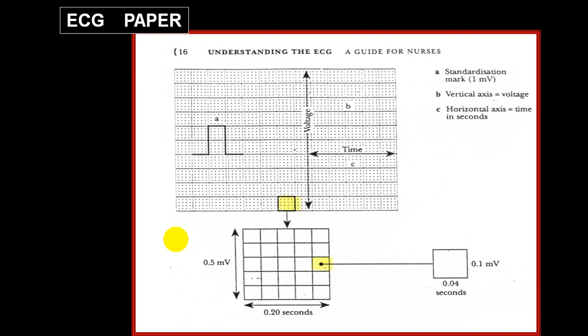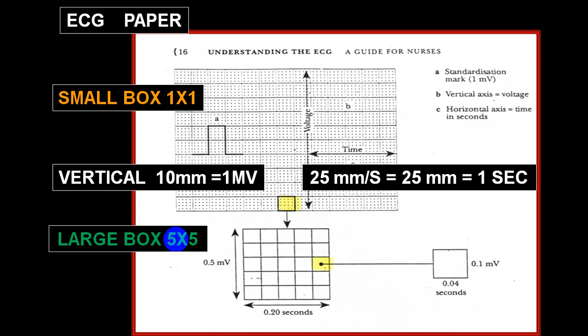Whenever an ECG machine is put on 25 millimeter per second speed, 25 millimeter of paper will come out in 1 second. That means one small box will be 1 millimeter, so it will be 0.04 second. Vertical amplitude is roughly 0.1 millivolt for a small square, and 10 small boxes, or 10 millimeters, will be equal to 1 millivolt.